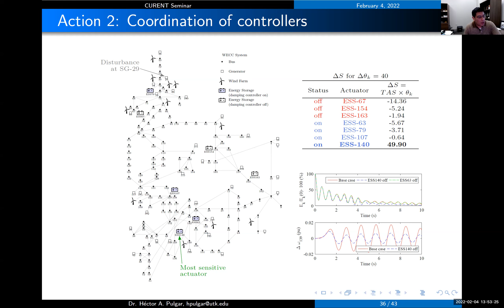So there are some drawbacks in this. Even though it worked, we proved that this scheme should work if we know these sensitivities. But the drawback is that these calculations are time consuming. And not only that, these sensitivities are going to depend on the operational condition, loading levels, unit commitment, and topological changes too. If you have a fault, you might have a line outage, and this sensitivity might change.